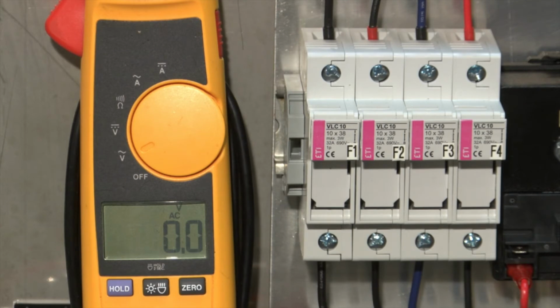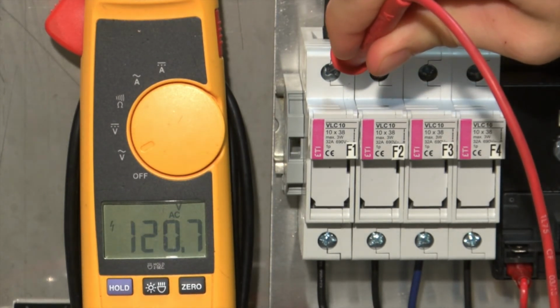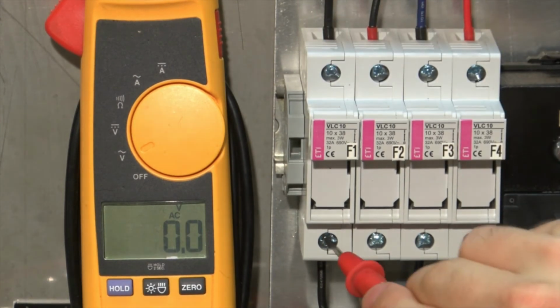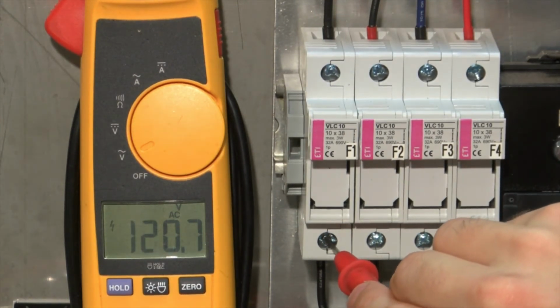The same rules apply when looking at the fuse block. Black is 120 on the primary side of the transformer. Blue is 48 volts on the secondary side of the transformer. And red is 24 volts on the secondary side of the transformer. To verify a fuse is good, use your corresponding neutrals on the transformer as discussed. To check the 120 volts, we will use one prong on the transformer's neutral on the primary side. Check the incoming power of the fuse as 120. Check the outgoing power of the fuse matches 120.